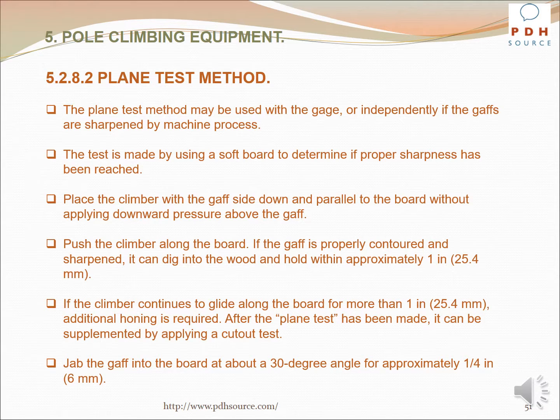The plane test method may be used with the gauge or independently if the gaffs are sharpened by machine process. The test is made by using a soft board to determine if proper sharpness has been reached. Place the climber with the gaff side down and parallel to the board without applying downward pressure above the gaff. Push the climber along the board. If the gaff is properly contoured and sharpened, it can dig into the wood and hold within approximately 1 inch. If the climber continues to glide along the board for more than 1 inch, additional honing is required.